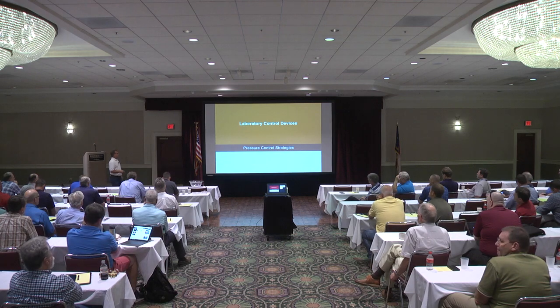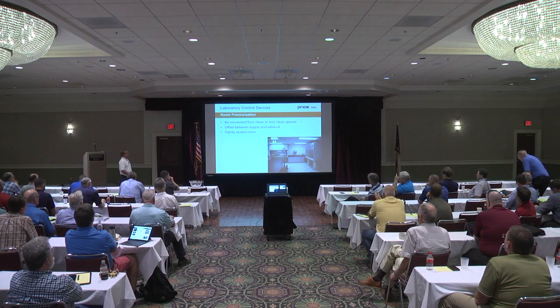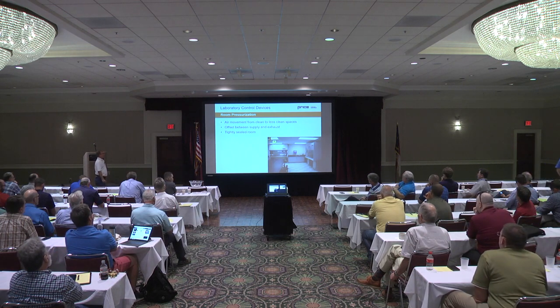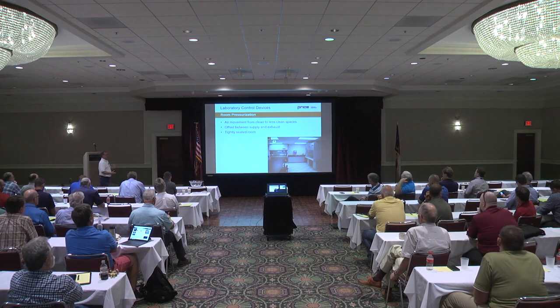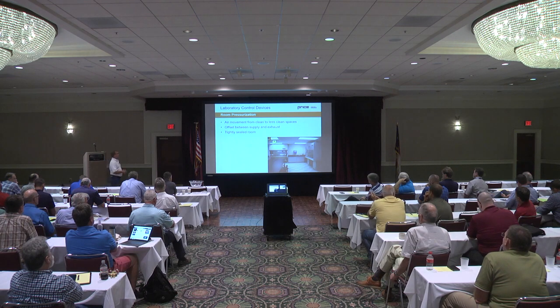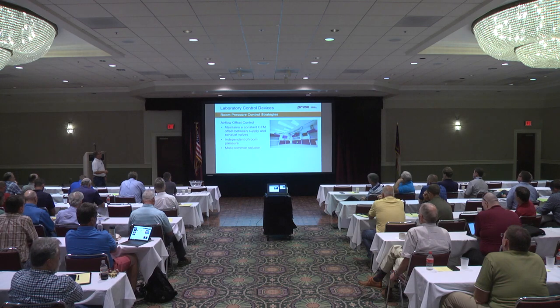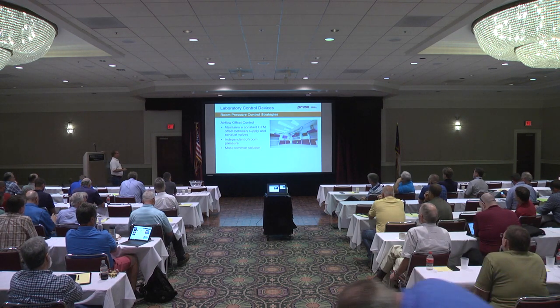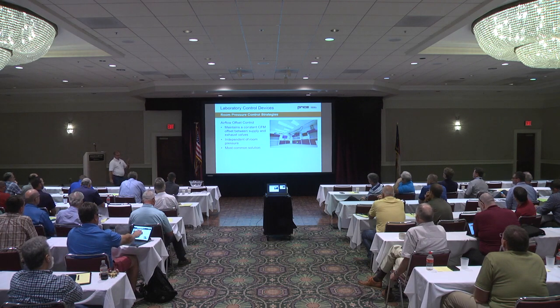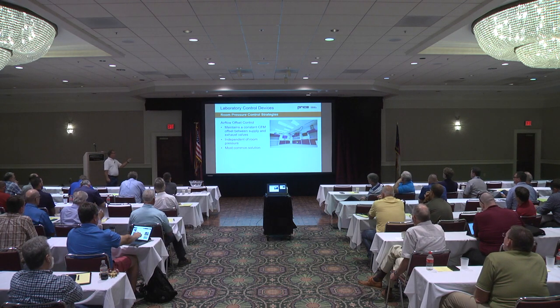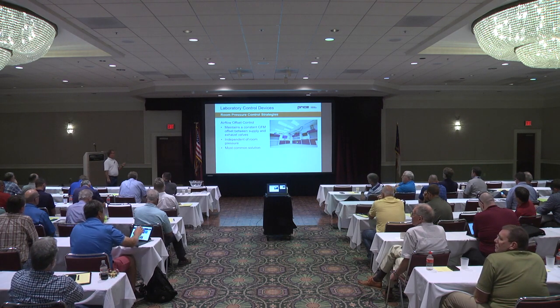A few laboratory pressure control strategies we involve with room pressurization all the time. Basically, in a lab environment, we're moving clean air to less clean air spaces. Normally, the lab is negative. It's got fume hoods. We've got an offset between supply and exhaust. Tightly sealed rooms will affect pressurization. Room pressure control strategies: airflow offset control, where you have a fixed difference between supply and exhaust that's maintained through any mode of the lab. You maintain a constant CFM that will deliver the pressure required for the lab space.